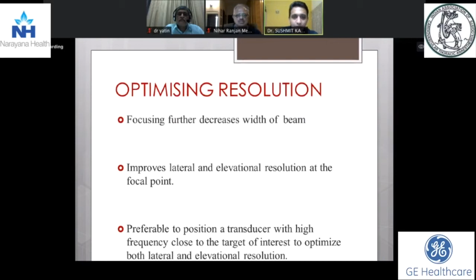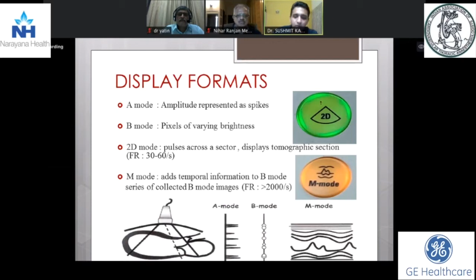So now, what are the various display formats? Once the information is received back, there are various display formats by which we can see it on the screen. The most primary method was A mode, in which the amplitude of the returning signals was shown as vertical spikes. This evolved into B mode, where instead of the vertical spikes, pixels of various brightness were denoted. Now what we usually use is 2D mode and M mode, which are variations of B mode. In 2D, instead of having a single B mode, the pulses are scattered across a sector to display a tomographic section.